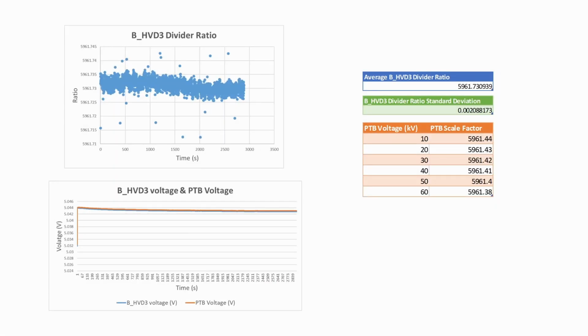So, does it work? Yes, it works. What you're looking at here in the first graph is the divider ratio plotted against time. The divider ratio is the fraction of the total applied voltage that we read across the last divider in the high voltage divider. The high voltage divider ratio is a scalar factor that you multiply that value by to get the total voltage applied across the divider. So we can see that this is pretty steady through time, which is good, which is what we want. So that's an indicator that the voltage divider is performing optimally.